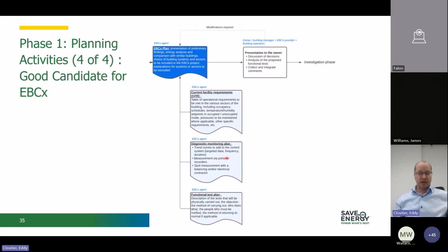The second document is the diagnostic monitoring plan, which presents all measurements needed to validate the proper functioning of the systems. Some data logging will be added to the control system, the BAS system. In some cases, measurements by portable recorder will be specified, or even sporadic measurements with a balancing contractor or electrician might be needed. Finally, the last document is the plan for the functional tests to be carried out. Functional tests are meant to validate how the system reacts, to detect any deficiencies to be corrected or lower performance than expected at design. This is a very important part of the investigation process.